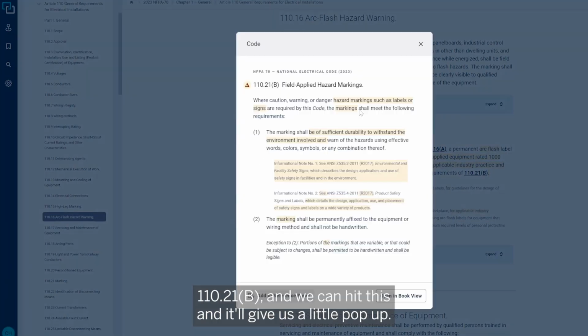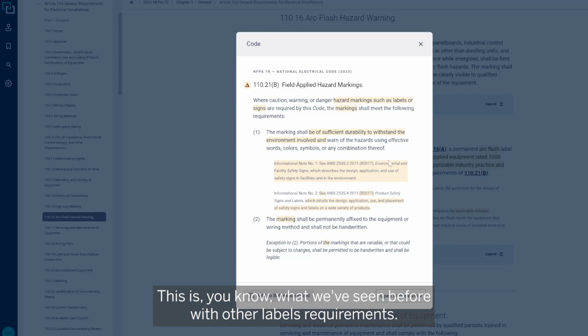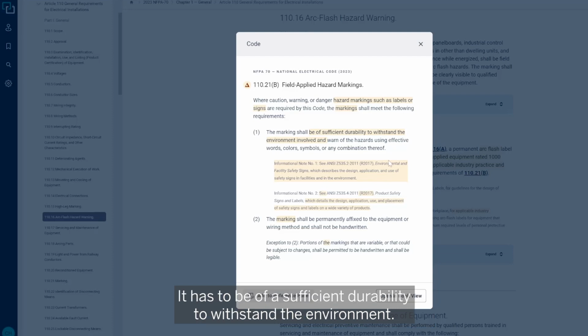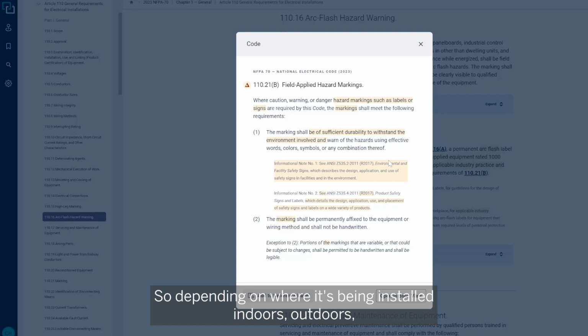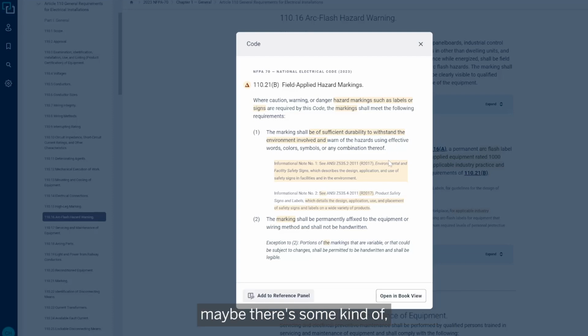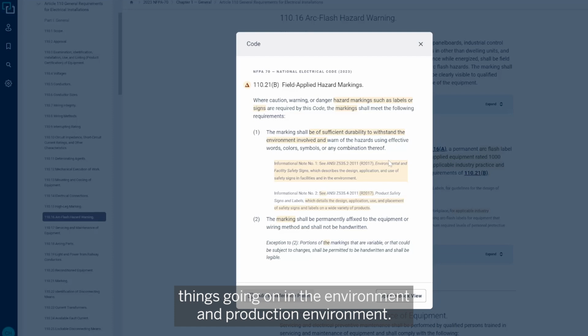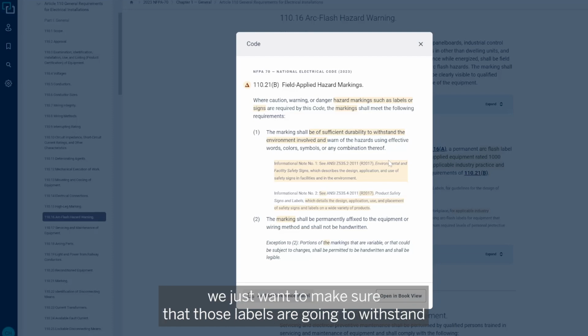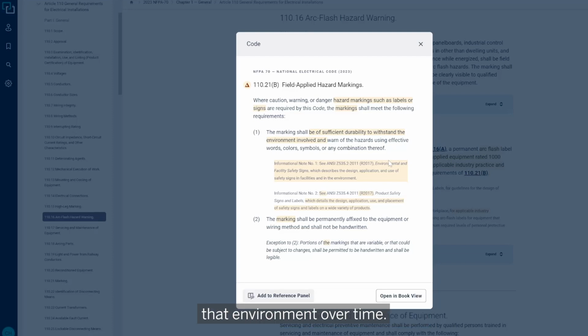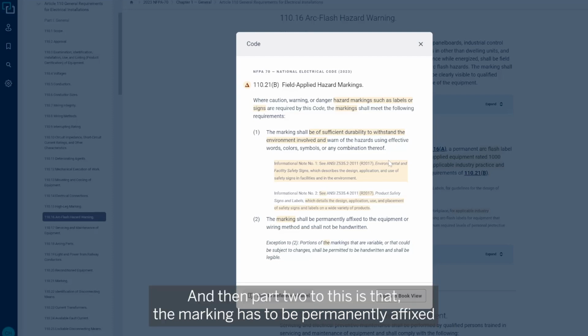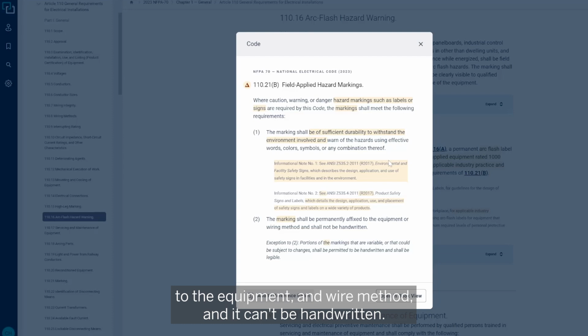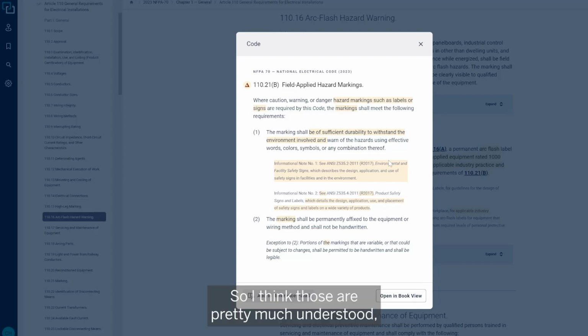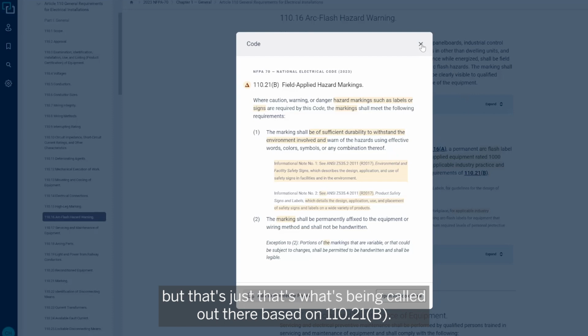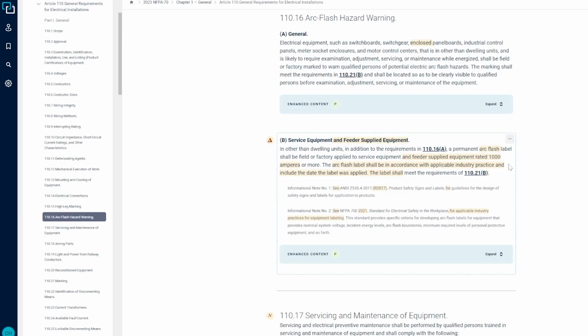110.21(B), and we can hit this and it'll give us a little pop-up. This is what we've seen before with other label requirements. It has to be of a sufficient durability to withstand the environment. So depending on where it's being installed, indoors, outdoors, maybe there's some kind of things going on in the environment and production environment. We just want to make sure that those labels are going to withstand that environment over time. And then part two to this is that the marking has to be permanently affixed to the equipment or wiring method, and it can't be handwritten. So I think those are pretty much understood, but that's what's being called out there based on 110.21(B).